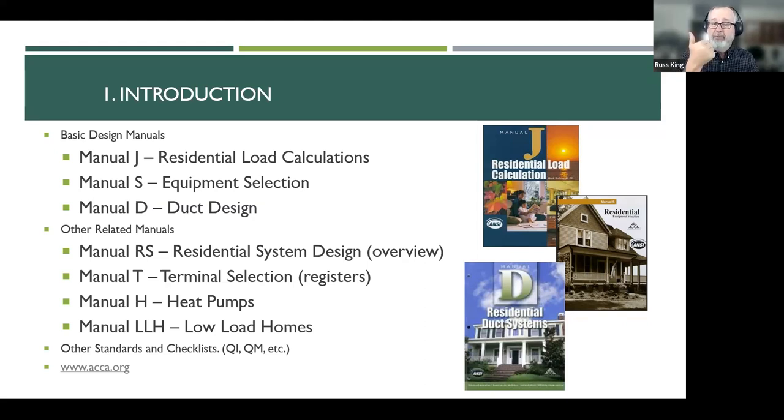I wasn't super picky about exact placement, but I was very picky about duct sizes. If they had the right duct sizes and the right equipment sizes, I considered that they followed my plans. I never worried much about velocity of air inside the ducts — face velocity coming out of the registers is different and is important because that's how you get your throw.